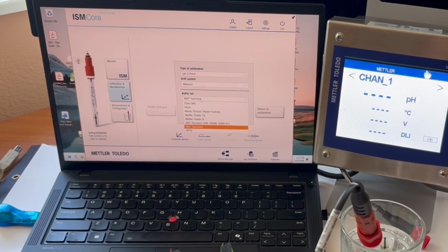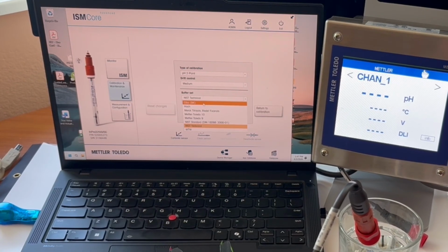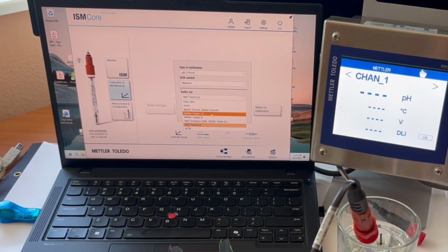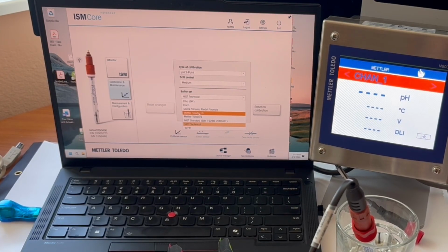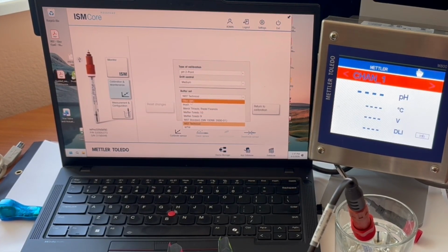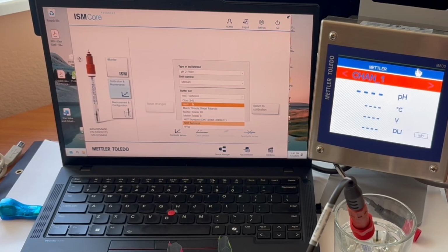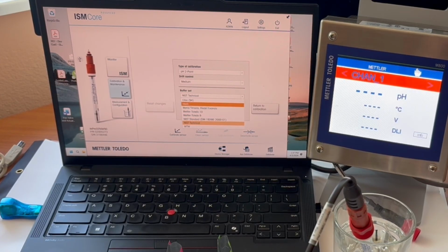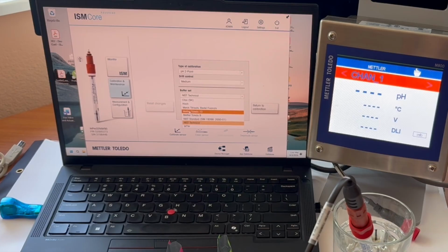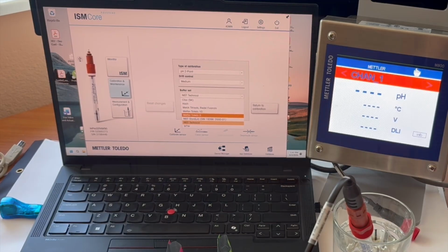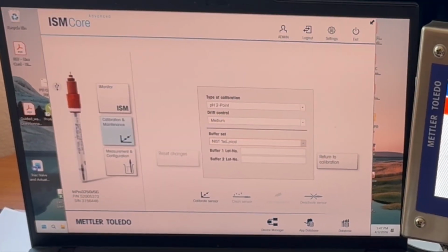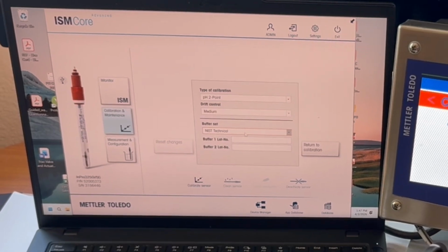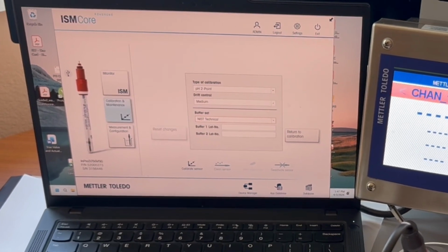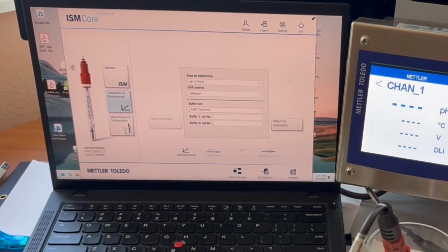The buffer set, I know some of the programs out there, you have to manually load these. These are all automatically provided from Mettler-Toledo. If you wanted to use some other solutions from other providers, they're not forcing you to use their buffers. You can buy it from Hach, you can get it from VWR, Fisher, Thermo Fisher. I typically just use NIST Technical. That's the one I use by default. That gives me 4, 7, and 10 for my buffer recognition when I'm doing temperature compensation.